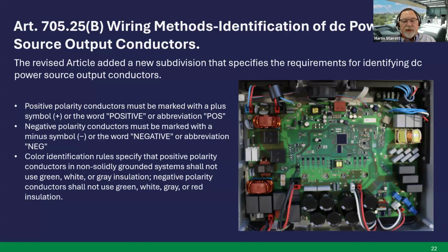Color identification rules specify that positive polarity conductors in non-solidly grounded systems shall not use green, white, or gray insulation, and negative polarity conductors shall not use green, white, gray, or red insulation. Next slide.